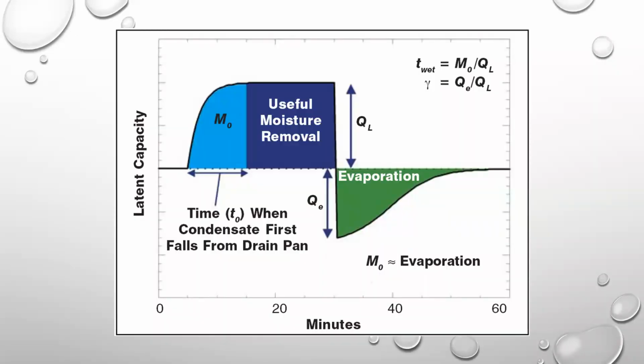This is out of an article from ASHRAE from 2011. And what it shows is runtime versus useful moisture removal. You have to have a certain amount of runtime before any moisture gets out of the system to the drain pan and out. And that's the useful moisture removal. If you don't get the minimum runtime, what happens is it evaporates right back in. So you're basically wasting energy because that evaporation also does cooling. So you'll be wasting energy.